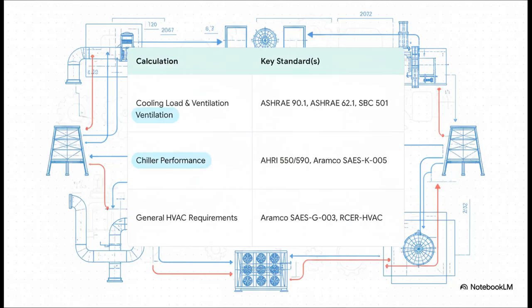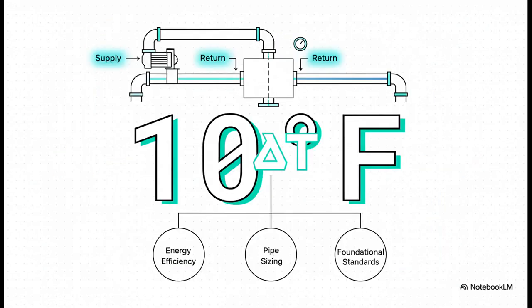Now this table, this is basically your cheat sheet. It shows you exactly how different tasks map to different codes. You're doing cooling loads, you're juggling ASHRAE and the SBC. Looking at chiller performance, you've got AHRI standards sitting right next to specific Aramco rules. This is your guide to getting the design right. And all those calculations lead to critical design targets. A perfect example is your chilled water temperature differential, or delta T, often set right at 10 degrees Fahrenheit. This one little number dictates so much: energy efficiency, pipe sizes, you name it. And it comes directly from those standards we just talked about.